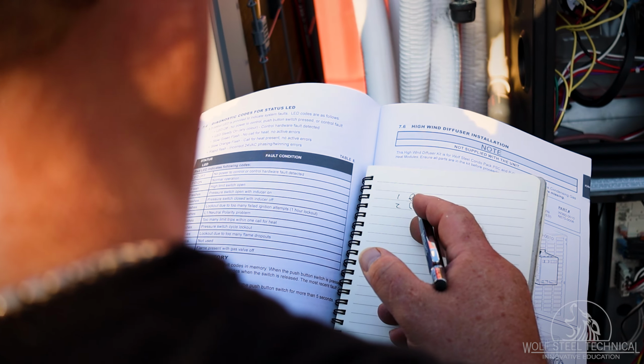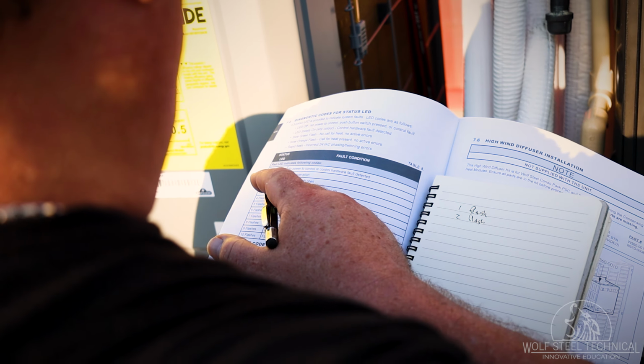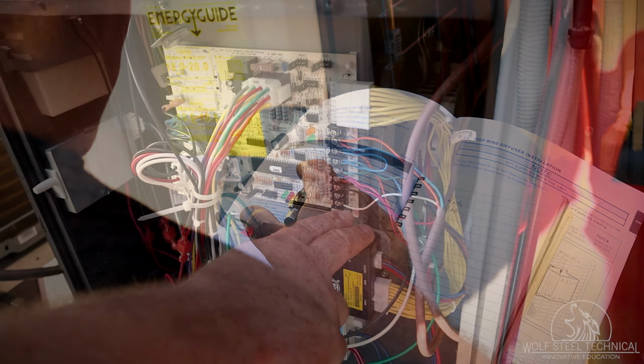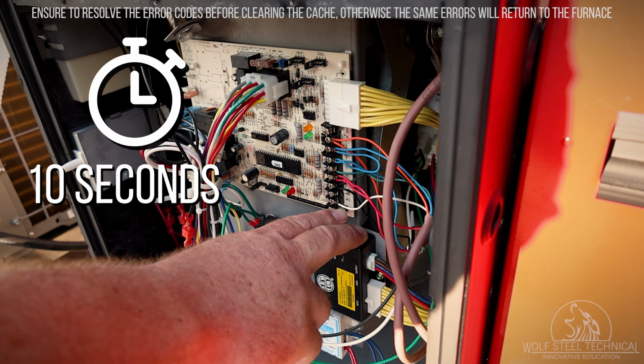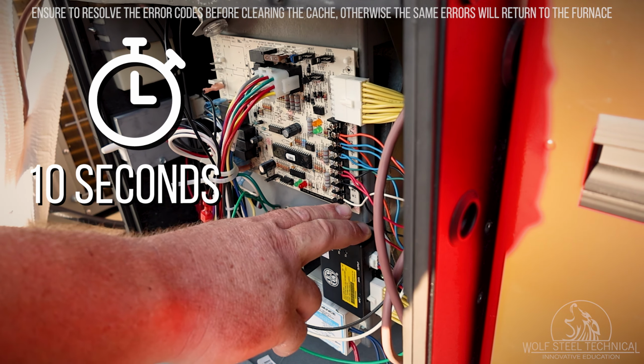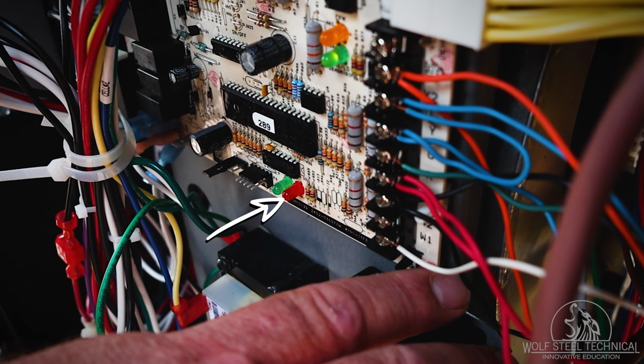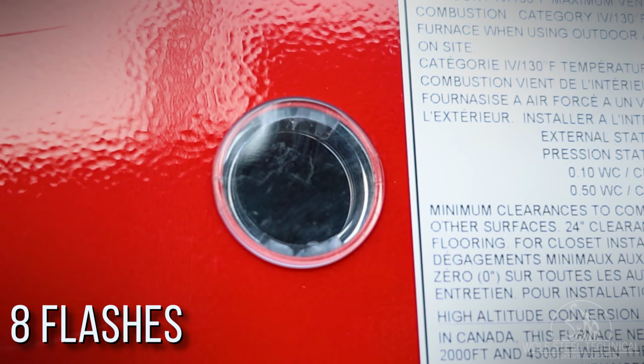The manual can be referenced for actionable services according to the number of flashes in the cache. Once all the codes have been resolved, clear the cache codes by pressing and holding the recall button for 10 seconds. You'll see a double flash once the cache has been cleared. When experiencing 8 flashes, this signifies a lockout due to too many flame dropouts.